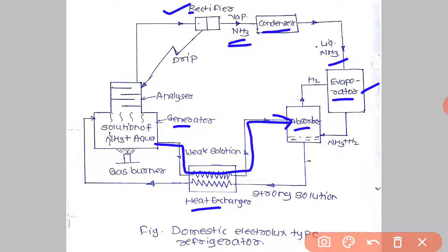Now the mixture of ammonia vapor and hydrogen is passed to the absorber, where ammonia is absorbed in water while hydrogen rises to the top, and it will flow back to the evaporator. So the ammonia coming out from the evaporator is absorbed by the weak solution and it becomes strong solution, and it will flow back to the heat exchanger, and from the heat exchanger it will flow to the generator. From here hydrogen will rise again and go to the evaporator, and these cycles continue.